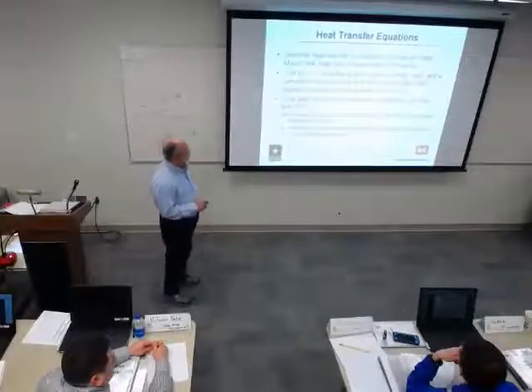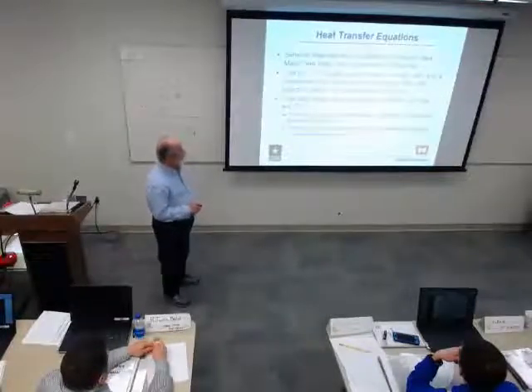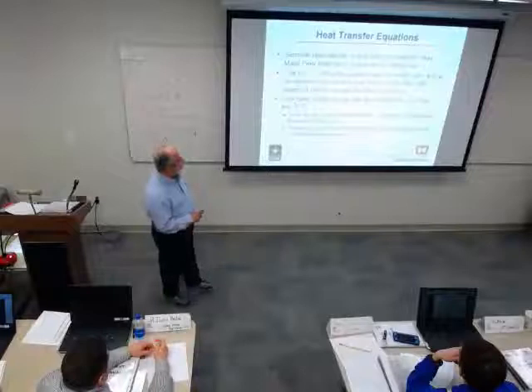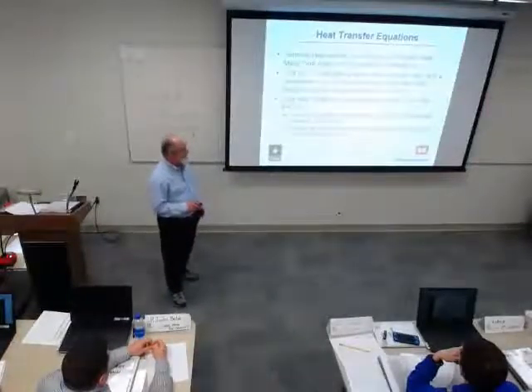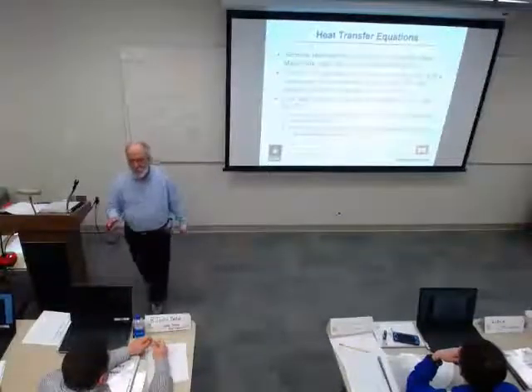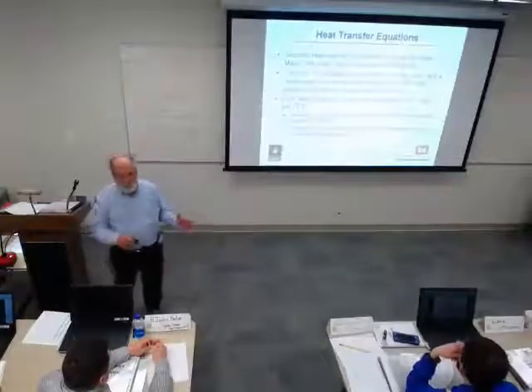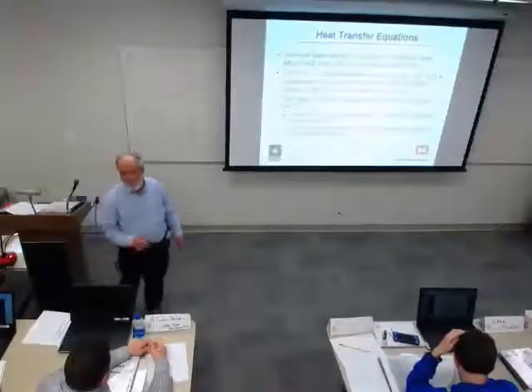Sensible heat transfer is a function of specific heat, mass flow rate, and temperature difference. That we kind of saw from that. 1.08 includes specific heat, humidity ratio, and a conversion from volume flow rate to mass flow rate based on density, as well as time. Oh, the hours to minutes. Yeah, there is a time, because we go cubic feet, BTUs per hour, and our flow rates and everything else is per minute. So that conversion factor includes the time part.